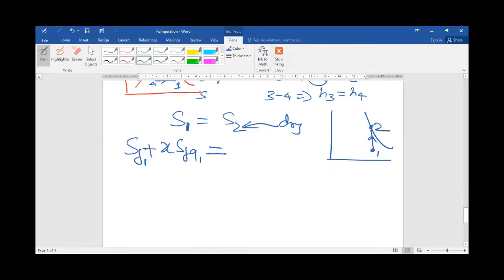Point number 2 is in dry. So when it is dry, you need to take only one value, that is SG. But point number 2 is related to 30 degrees Celsius. Point number 1 is related to minus 10 degrees Celsius. So these two values you copy from the minus 10 degrees Celsius table, and this value you take from the 30 degrees Celsius table.